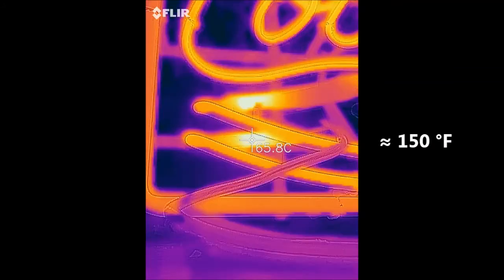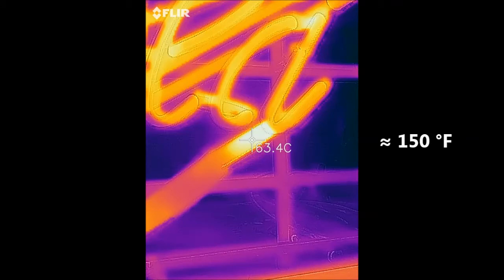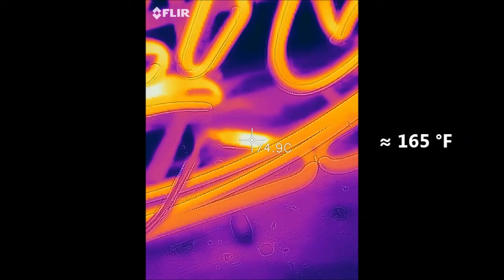You often find a worn electrode like this because it gets much hotter than the others. All the electrodes on this sign were in nice range. The green tubes were a bit warmer but I think still okay.